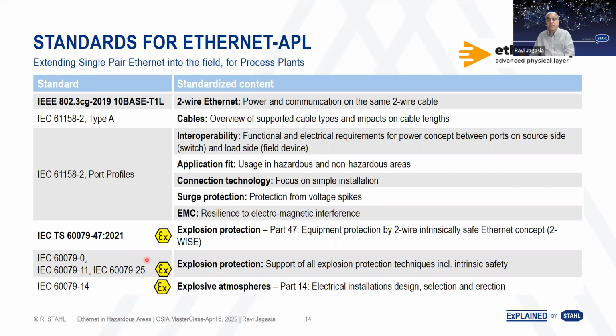And then, of course, we have the IEC standard 60079, the -11 and the -25, which are the explosion protection standards for hazardous areas. The -14 was also the requirements from an installation perspective. All these standards are adopted under UL 60079. So there are some changes, but the broad brush is that these standards were also adopted into UL 60079 under the AEx, or what is also called the NEC 505 standards. So more on this a bit later.